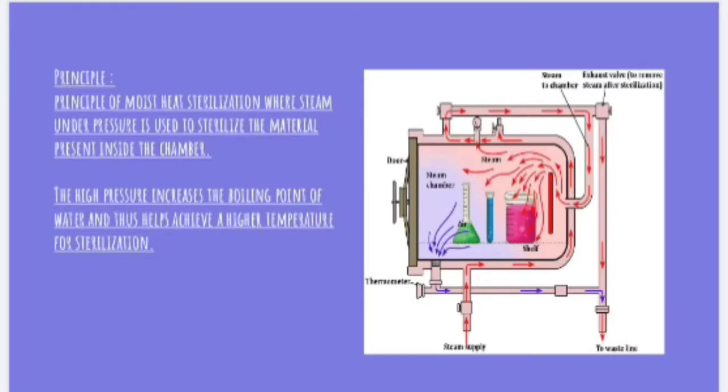Once the sterilization phase is completed, the pressure is released from the inside of the chamber through the valve. The pressure inside the chamber is then restored back to an ambient pressure while the components inside remain hot for some time.